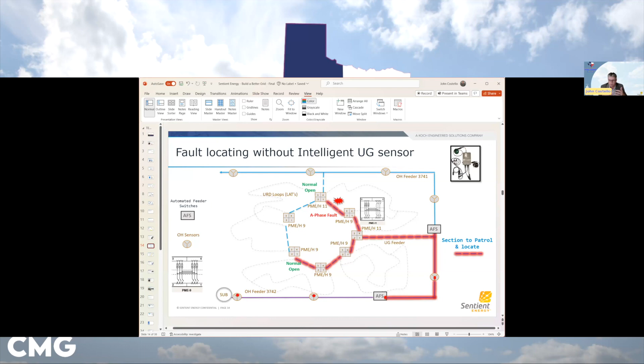This is a little more complicated than the diagram I showed before. Prior to the installation of underground sensing, you can see overhead sensors in the lower right quadrant, with one in the faulted section. At this point all you know is that you have a fault—you don't know if it's overhead or underground, just that it's somewhere in that red highlighted area. This is before any underground sensing is done.